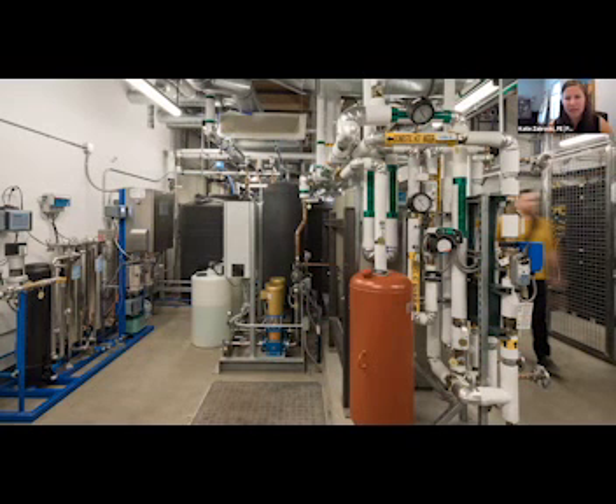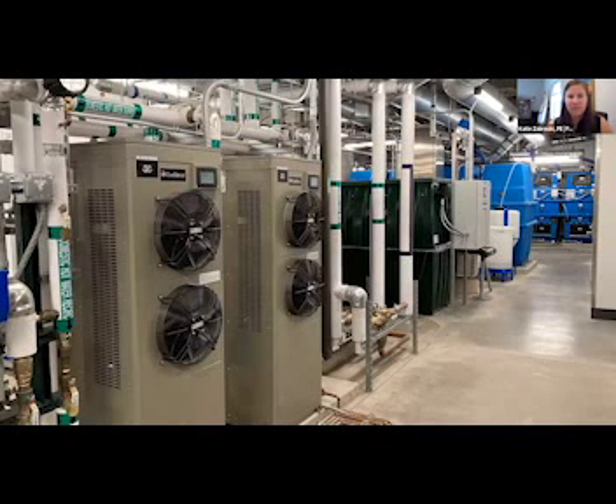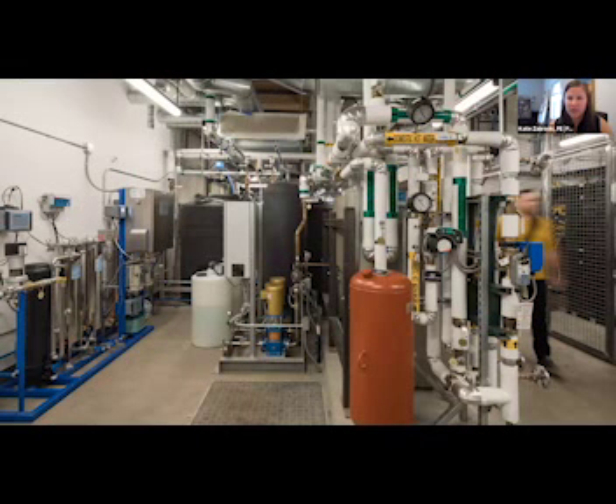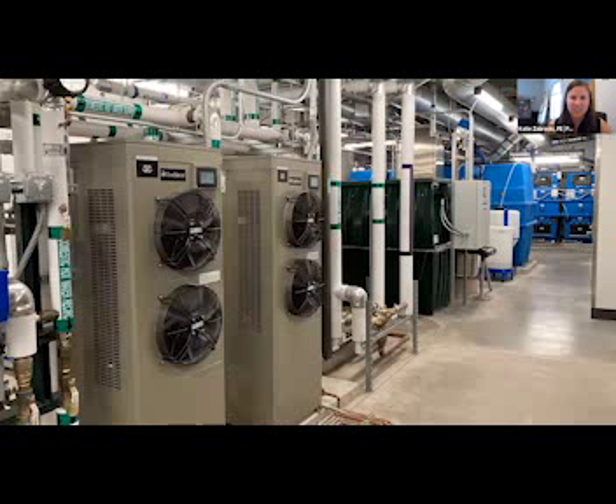Looking over to the right, you can see our domestic water heaters — we have 2 heat pump domestic water heaters that produce all of the domestic hot water for our sinks, lavs, and showers. They're positioned directly adjacent to this mesh wall area, which is our main MDF tech area, so we have a heat source there, and the heat pump water heaters pull heat from the ambient air in our room. It was a nice symbiotic relationship between the water heaters wanting to absorb heat and the IT equipment rejecting that heat.